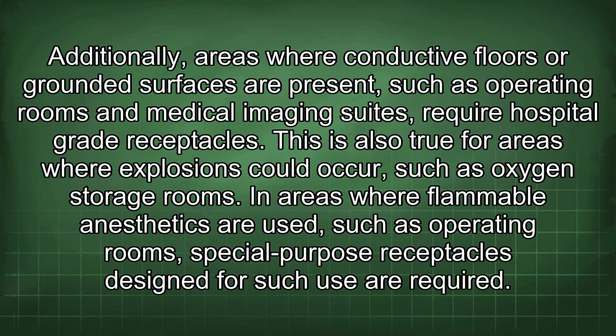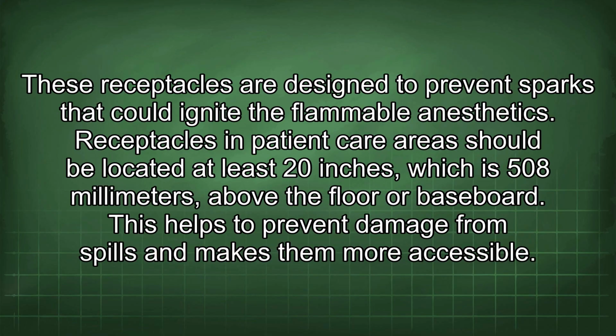Additionally, areas where conductive floors or grounded surfaces are present, such as operating rooms and medical imaging suites, require hospital-grade receptacles. This is also true for areas where explosions could occur, such as oxygen storage rooms. In areas where flammable anesthetics are used, such as operating rooms, special-purpose receptacles designed for such use are required. These receptacles are designed to prevent sparks that could ignite the flammable anesthetics. Receptacles in patient care areas should be located at least 20 inches, which is 508 millimeters, above the floor or baseboard. This helps to prevent damage from spills and makes them more accessible.